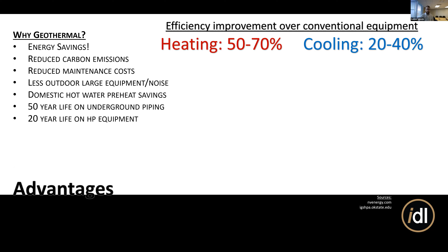So yes, pumps can be a significant cause of energy use within these systems. I look forward to talking about that shortly. They can also be linked with your domestic hot water system and used to preheat it. The underground piping can last anywhere from 25 to 75 years, based on what I could find from Canada's version of DOE. And the heat pump equipment itself is looking at about a 20-year lifespan. So when we're looking at payback periods and costs, those are a couple things to keep in mind.